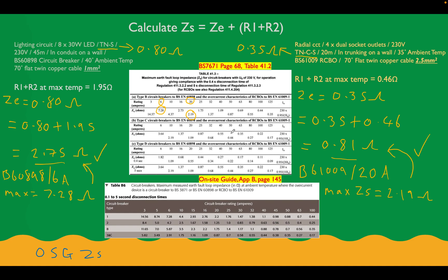BS7671 is the large brown book, which has comprehensive details of every single thing we could consider with requirements for electrical installations. Whereas the on-site guide is a baby version of this, which has details which we'd use whilst we were on-site. So what I'm trying to point out here is the ZS values in the BS7671 are 100% values. 100%. So ZS in BS7671, the big brown book, is 100% values. When we're doing circuit design, this is the values we want to choose. We want to pick them from this book. And the on-site guide ZS, these are 80% values because these already take into account ambient temperature, et cetera, because it's for use on-site. Designing a circuit in an office like we're doing, we're going to use these values.